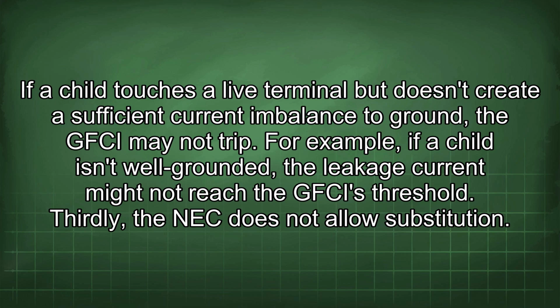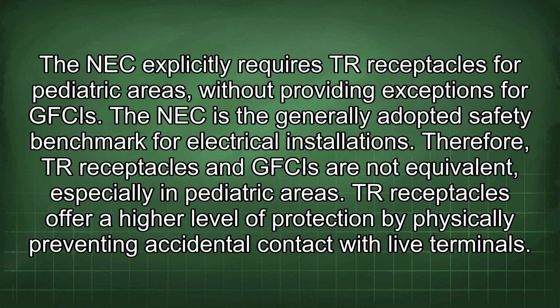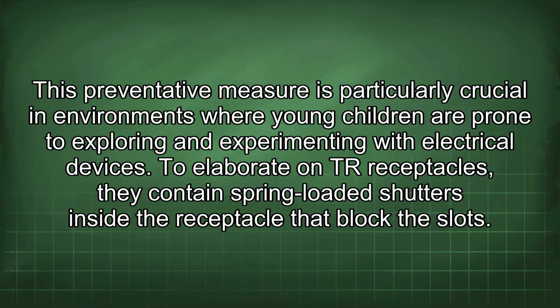Thirdly, the NEC does not allow substitution. The NEC explicitly requires TR receptacles for pediatric areas, without providing exceptions for GFCIs. The NEC is the generally adopted safety benchmark for electrical installations. Therefore, TR receptacles and GFCIs are not equivalent, especially in pediatric areas. TR receptacles offer a higher level of protection by physically preventing accidental contact with live terminals. This preventative measure is particularly crucial in environments where young children are prone to exploring and experimenting with electrical devices.